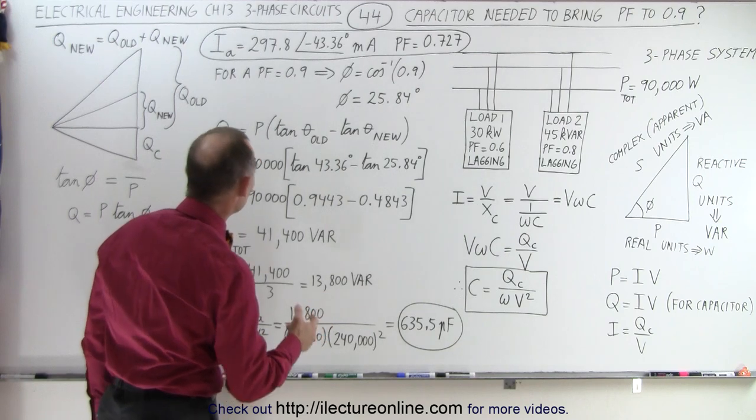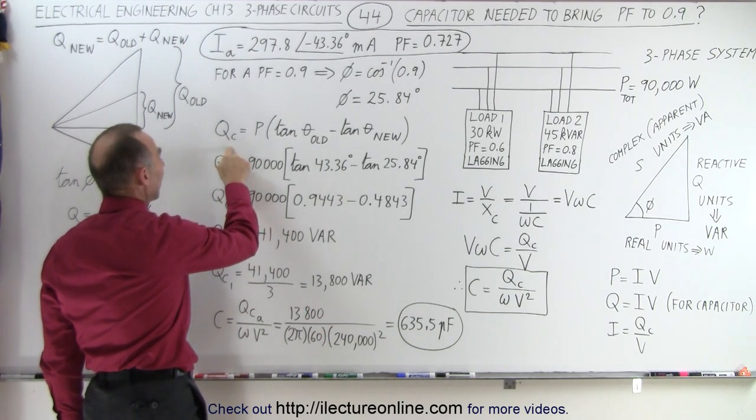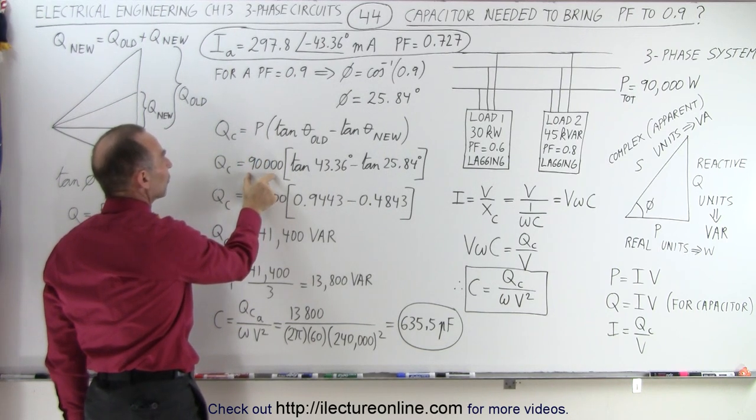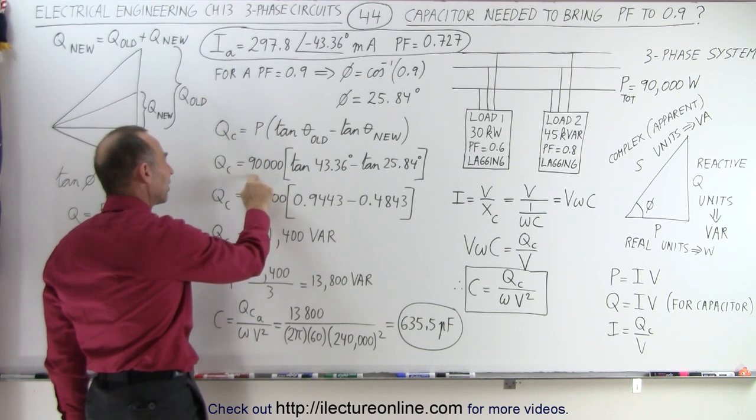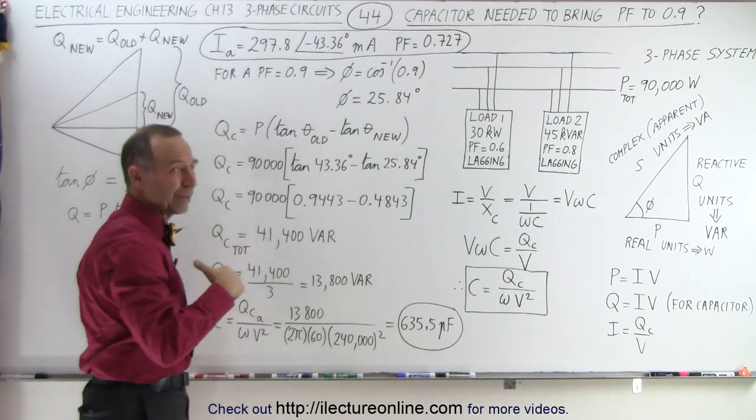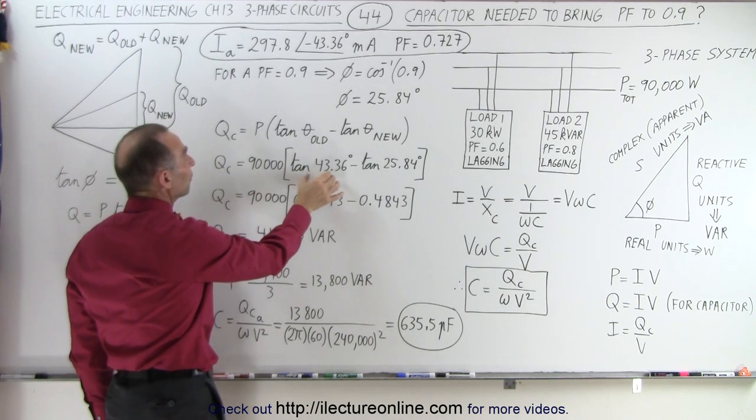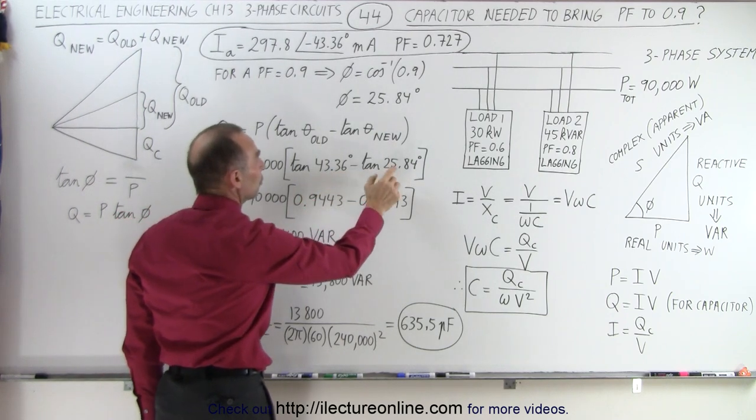We also need to know that the reactive power of the capacitor can be found by saying, I have the original power, which was 90,000 watts, or in this case, since we're talking about reactive power, it's 90,000 VAR, times the tangent of the old angle minus the tangent of the new angle.